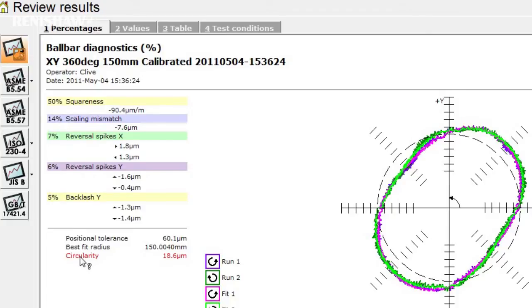If you have carried out a calibrated test, then just above circularity on the display is best fit radius. This is the radius of the circle that best fits the captured data and is shown on the plot as a dotted line.